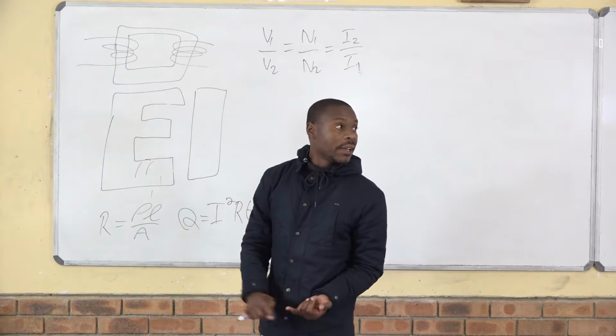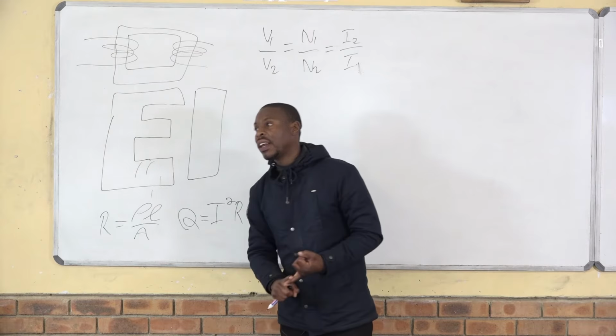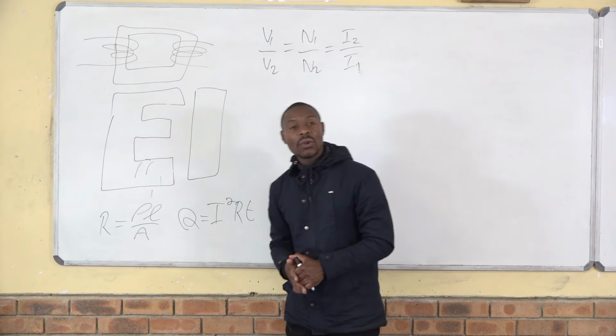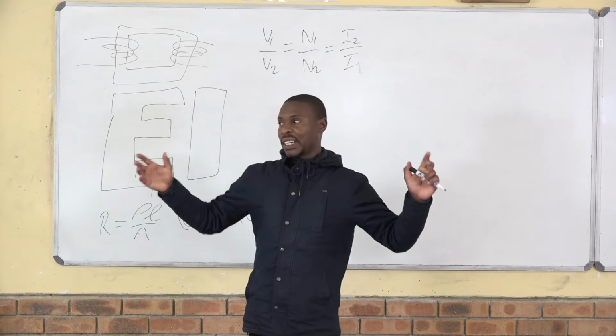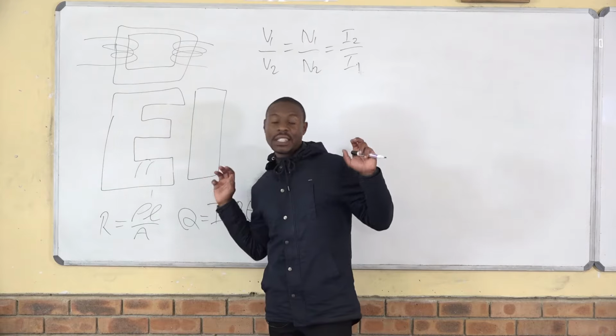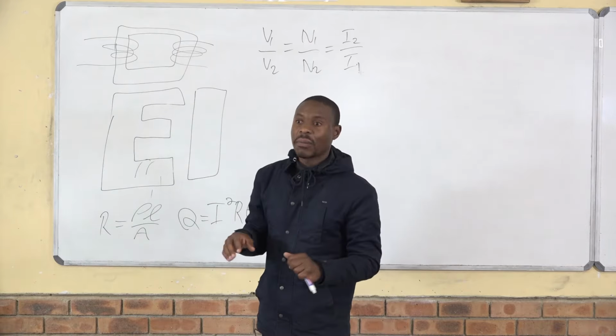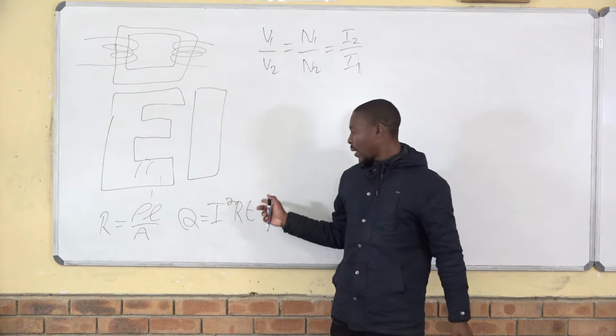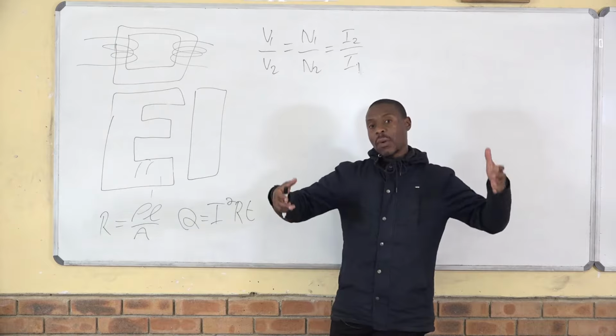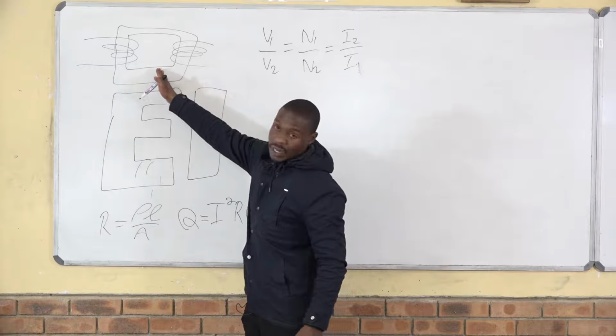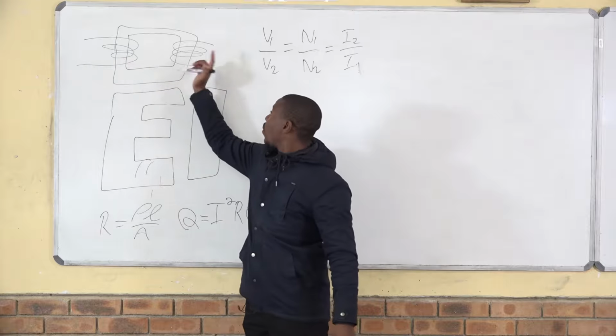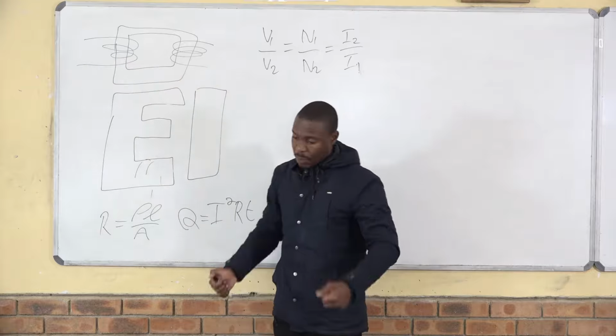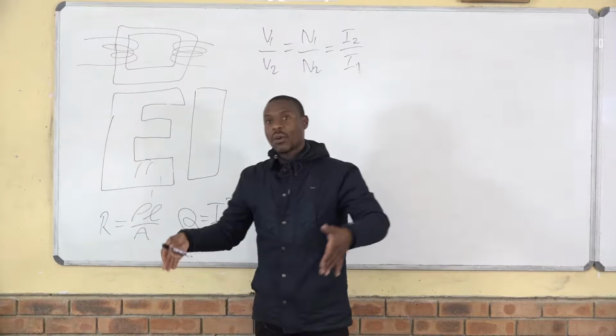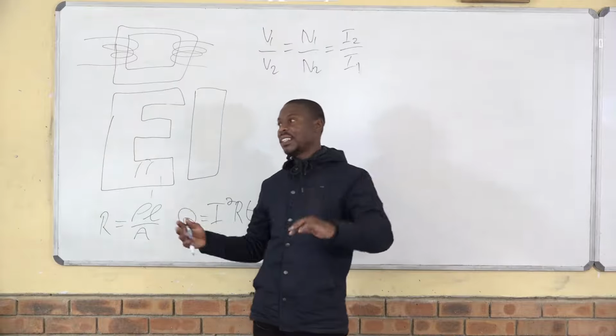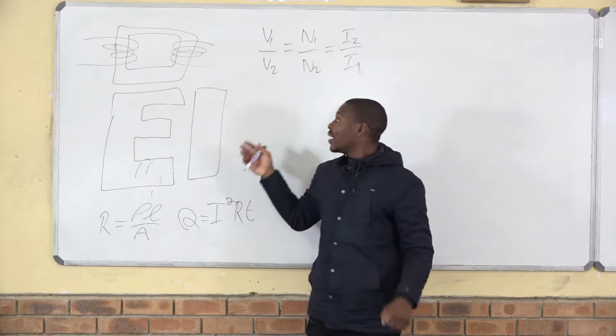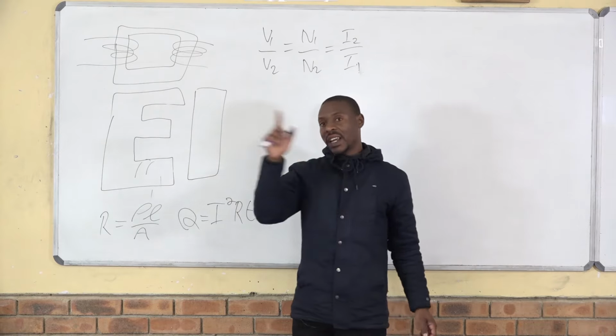So we have 2 types of cooling. We have oil cooling and air cooling. Under air cooling, you'll find that where a transformer is mounted, they put fans outside it. These fans blow air through the transformer. And then on the oil cooling, you'll find that the windings of a transformer, let's say for this one, they take that core with its windings, and then they deposit it inside the corrugated tank of a transformer. Then they seal it, they put a corrugated tank. That's how it's being cooled. So the oil will circulate inside.